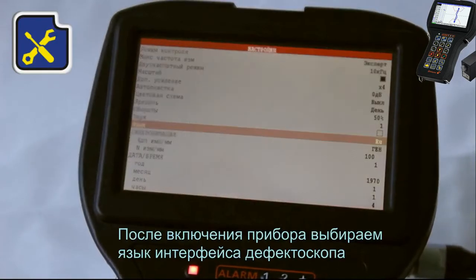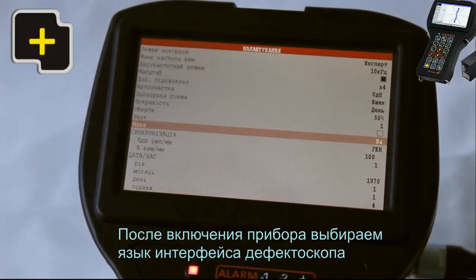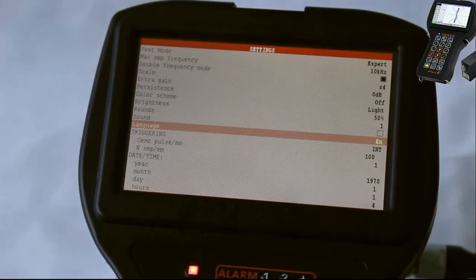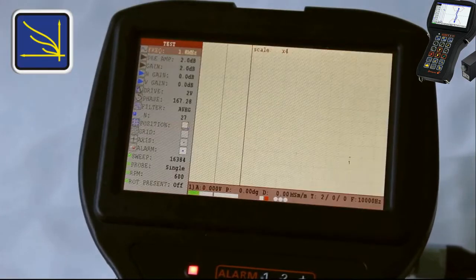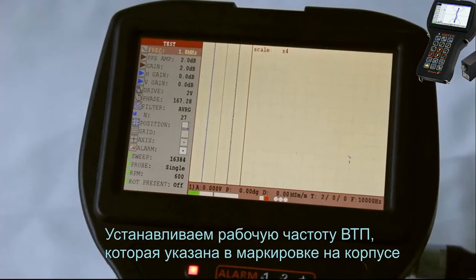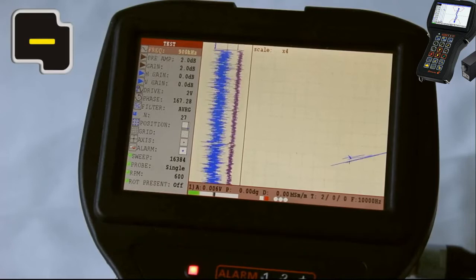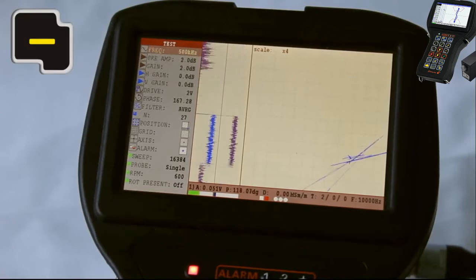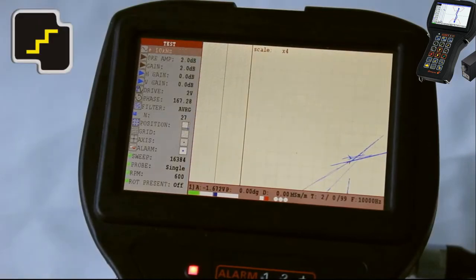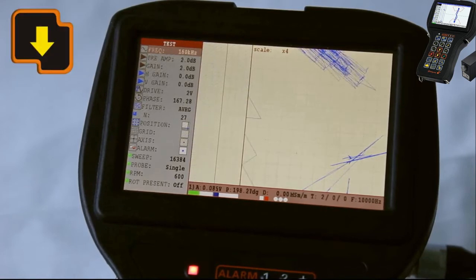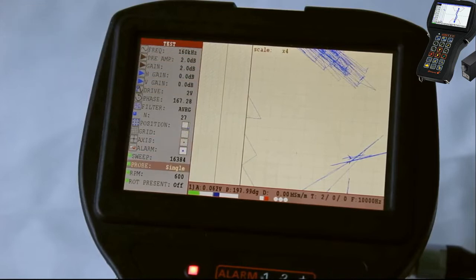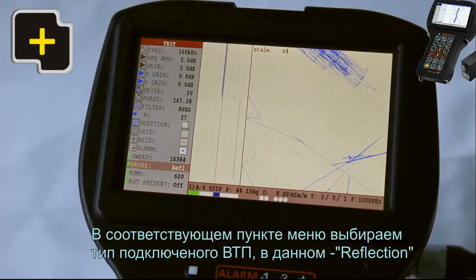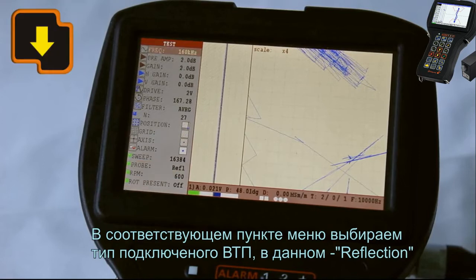After the instrument was switched on, select the language. Set up the operating frequency of the EC probe that is specified on the housing. In a relevant menu item, select the type of the connected ECP, in our case, reflection type probe.